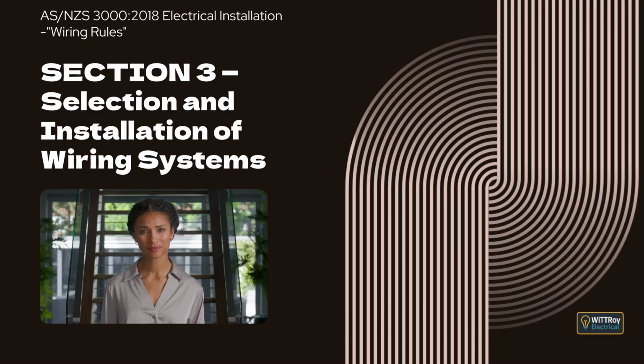The clause also explains that covers of wiring enclosures containing unsheathed cables must be securely retained and, where readily accessible, must not be removable without tools. Clause 3.10.2.2 Change of wiring enclosures. This clause explains that any change from one type of wiring enclosure to another must be made either at a switchboard or by using a suitable device that fully protects the conductor insulation and maintains continuity of conductive enclosures.